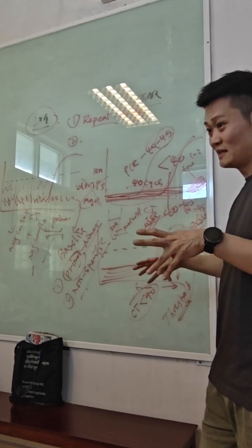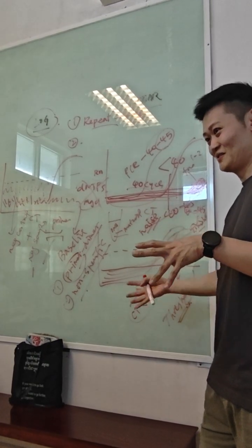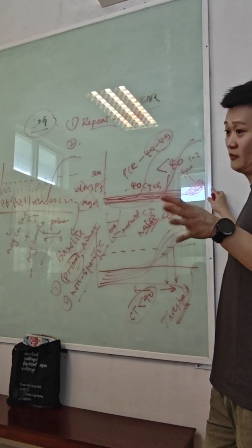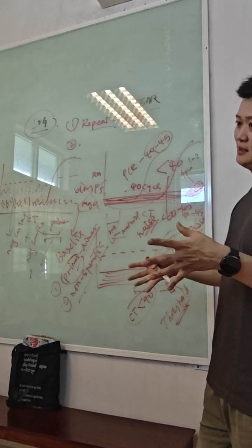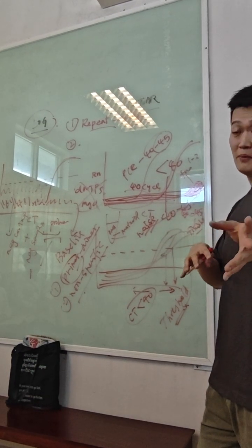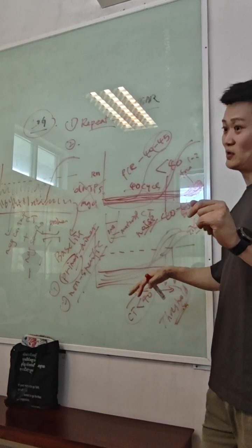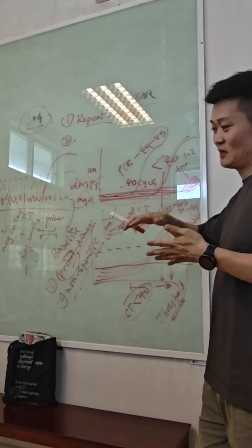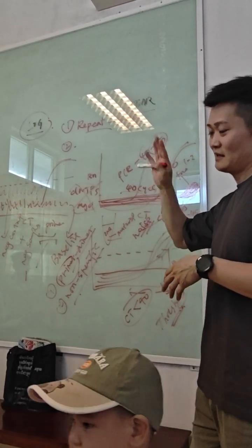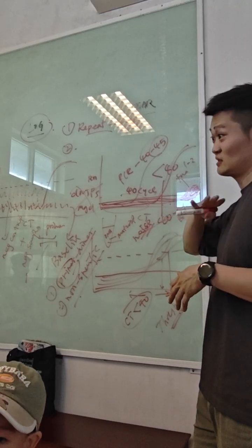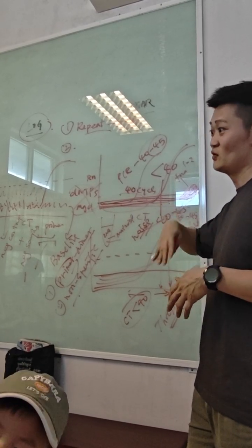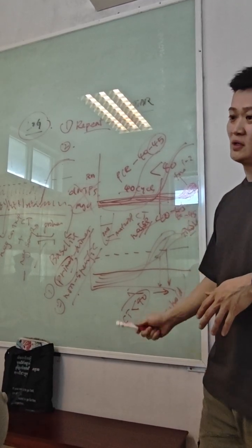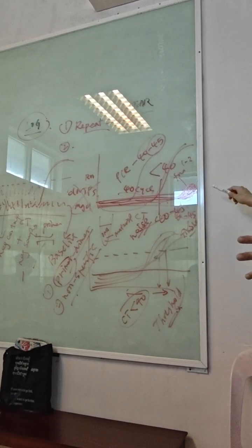It depends on whether you have finished the same kit already or not, because it depends on your volume also. Normally for the lot number of the reagent, we will give you the same lot number, and we have already tested it in the QC department in the factory to make sure everything is okay. But sometimes, as I told you, maybe the machine, because every time you turn it on, the light and everything fluctuates, not stable for the light source and the machine running. So there are some factors that also affect this. So that's why you need to confirm using this.